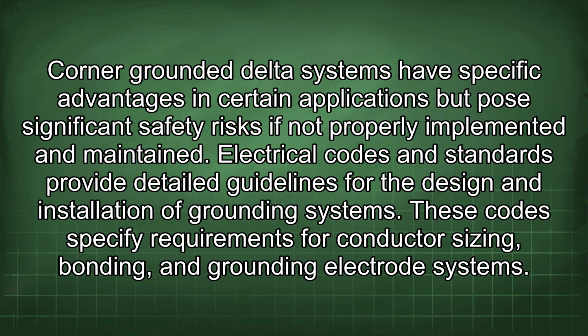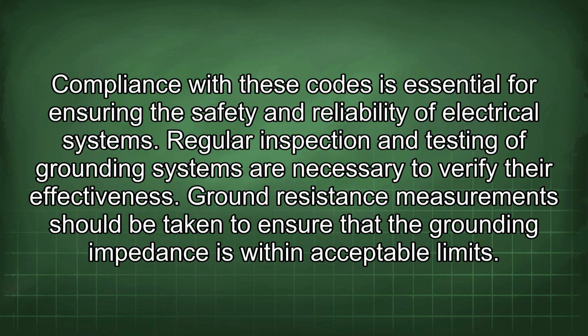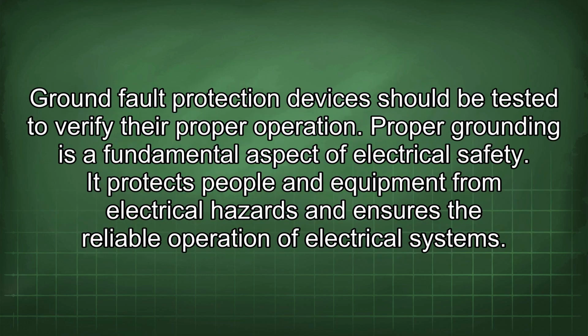Electrical codes and standards provide detailed guidelines for the design and installation of grounding systems. These codes specify requirements for conductor sizing, bonding, and grounding electrode systems. Compliance with these codes is essential for ensuring the safety and reliability of electrical systems. Regular inspection and testing of grounding systems are necessary to verify their effectiveness. Ground resistance measurements should be taken to ensure that the grounding impedance is within acceptable limits. Ground fault protection devices should be tested to verify their proper operation.